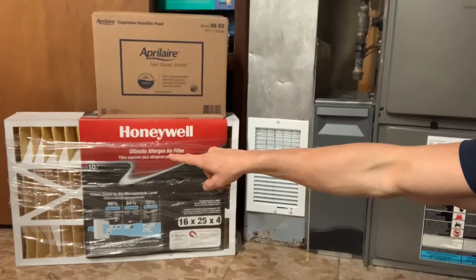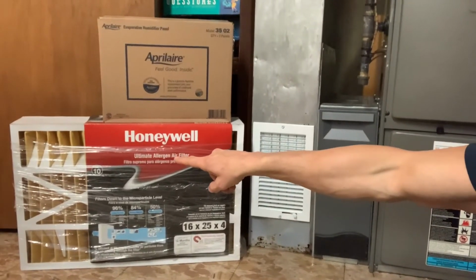Now this is the only area in your home that I want you to get the cheapest filters, okay? So all these filters, like this one for example, has an FPR rating of 10. The filters are going to come in two different ratings, MERV or FPR. And the higher the number, the more restrictive the filter is. We want you to get the cheapest, lowest MERV filter you can possibly get, which is usually a 3 or a 5. If they're out of a number, get the next lowest number.